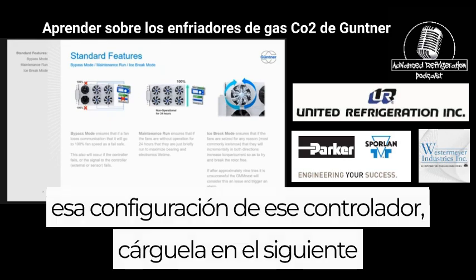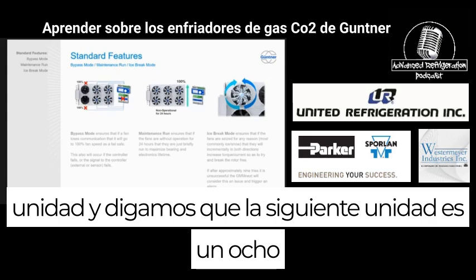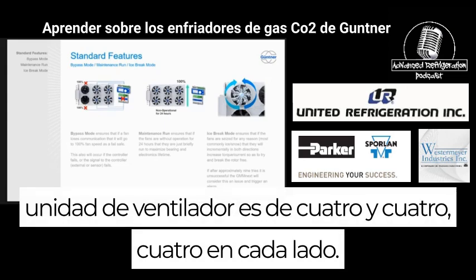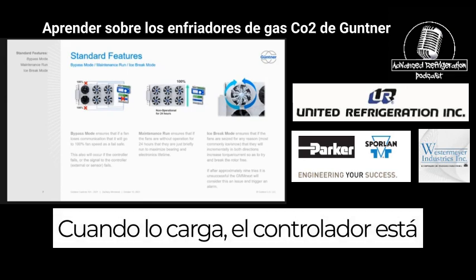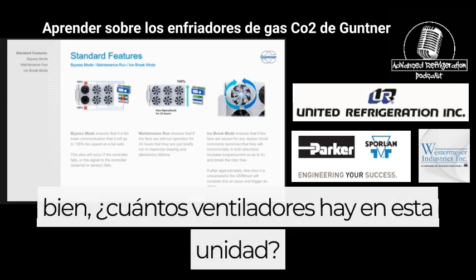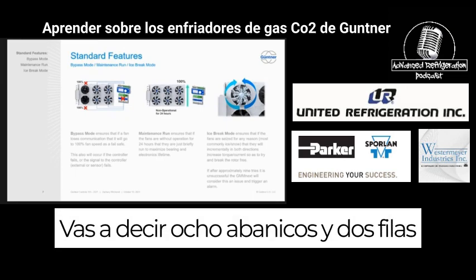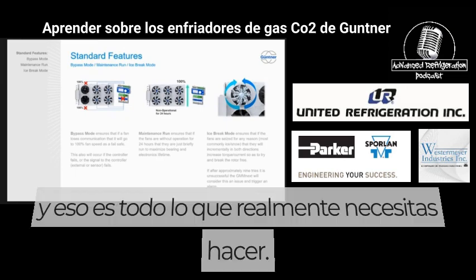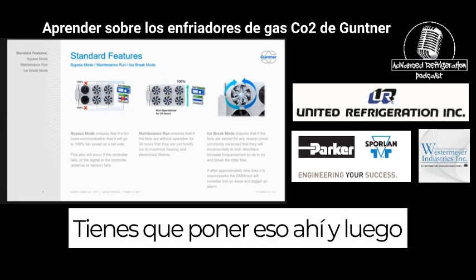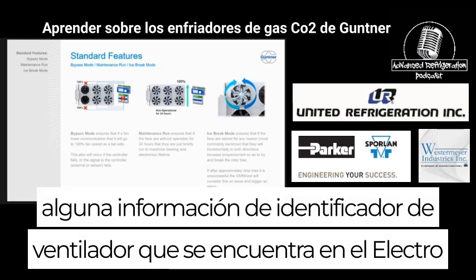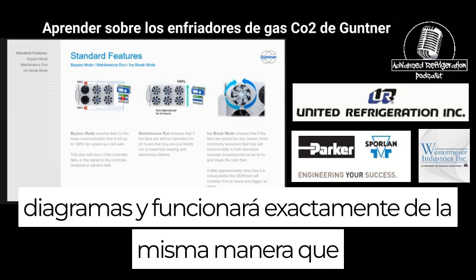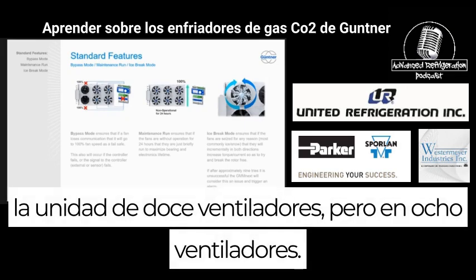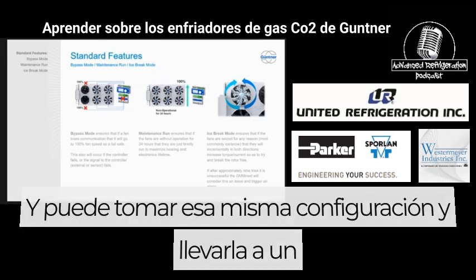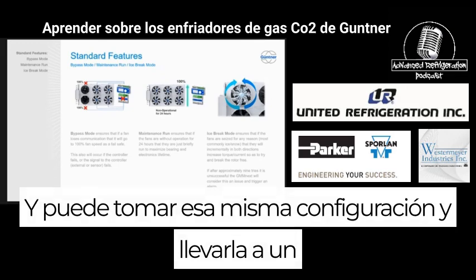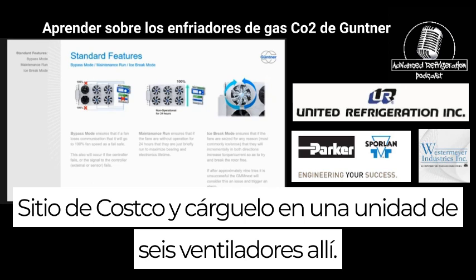You can pull that configuration from that controller, load it onto the next unit. And let's say the next unit is an 8 fan unit, 4 on each side. When you load it up, the controller is going to ask, okay, how many fans are on this unit? You say 8 fans and 2 rows, and that's all you really need to do. You put that in there and then some fan identifier information that's located on the electrodiagrams, and it'll operate the exact same way as the 12 fan unit, but with 8 fans. And you can take that same configuration to a Costco site and load it on a 6 fan unit there.